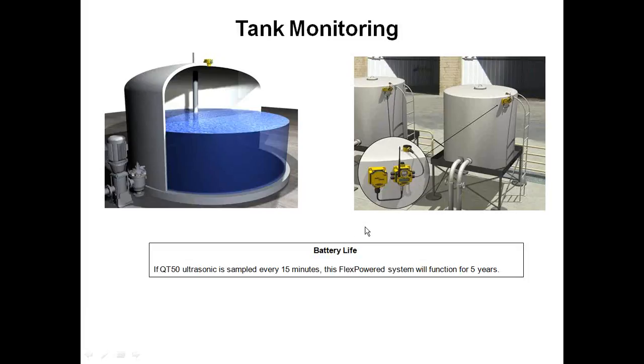One of my rule of thumbs with flex power is only use it when you have to. Anytime you introduce a battery into the situation, it's just another maintenance issue. And all of our flex power units come with the capability that if you did have power there, you can actually disconnect the battery and run 10 to 30 volts to it and do either battery or DC supplied power. But tank level is one that we do a lot. And again, depending on your sensor, this could be pressure sensor, could be an ultrasonic. We can do a characterization test that'll tell you how long the battery on that will last.